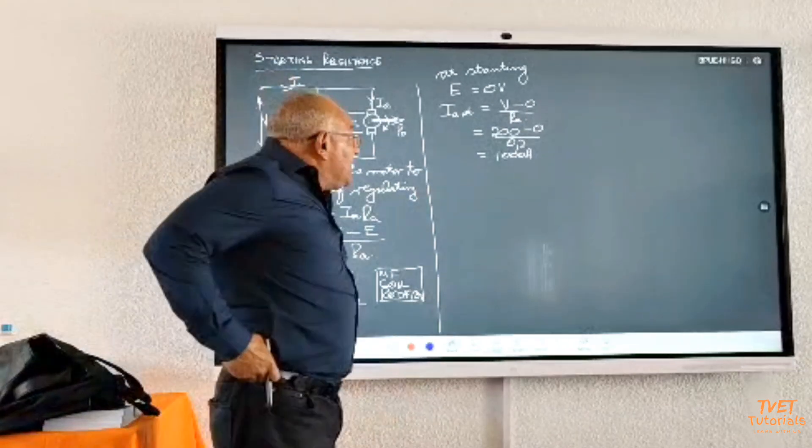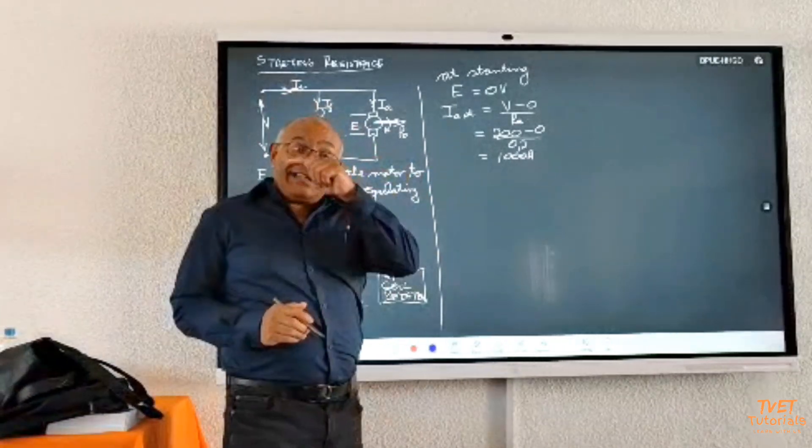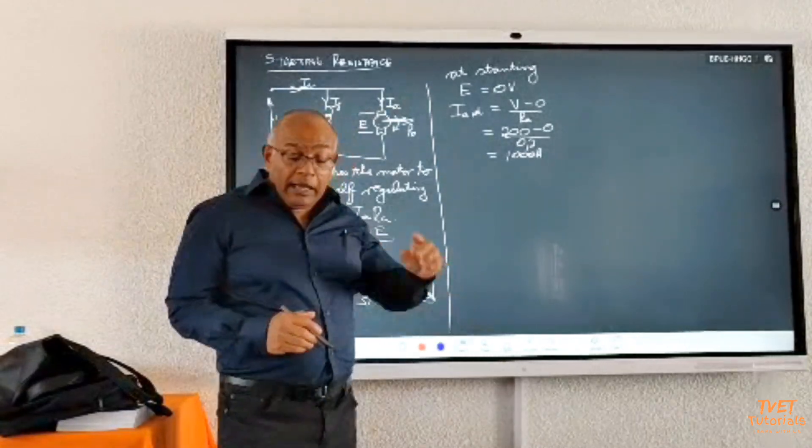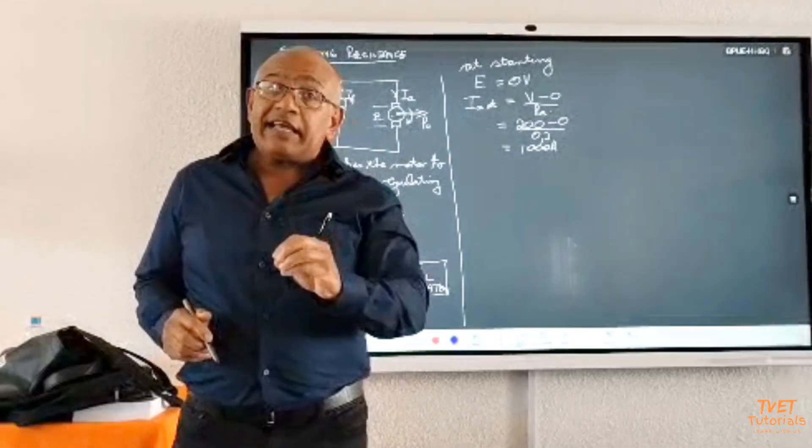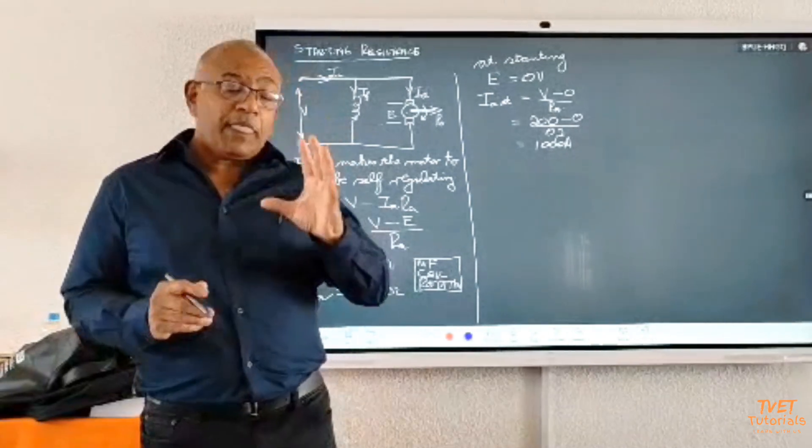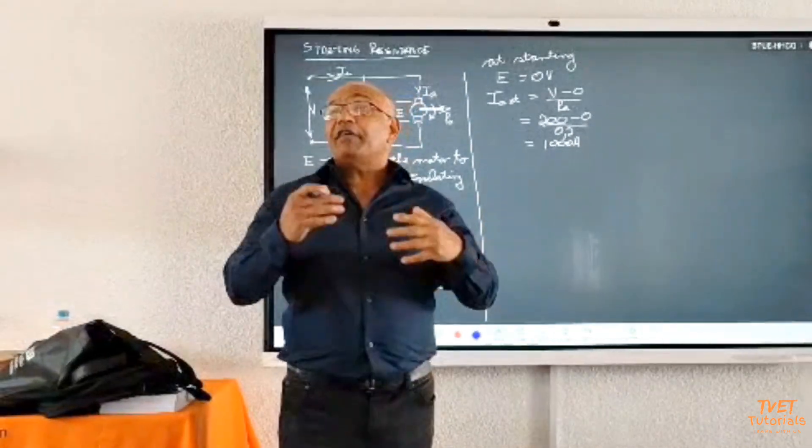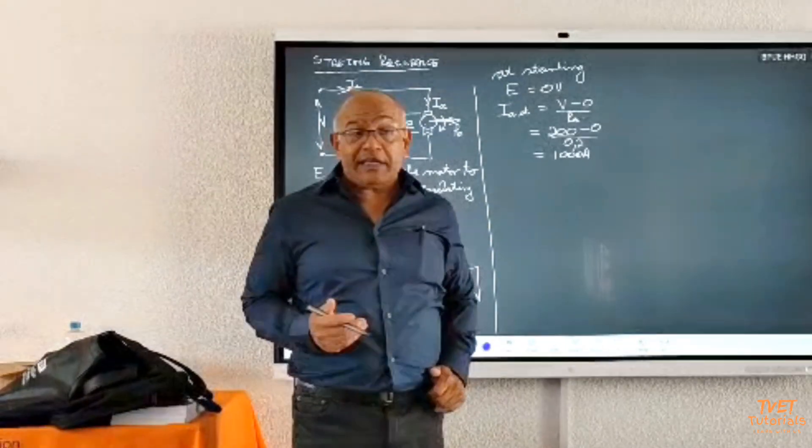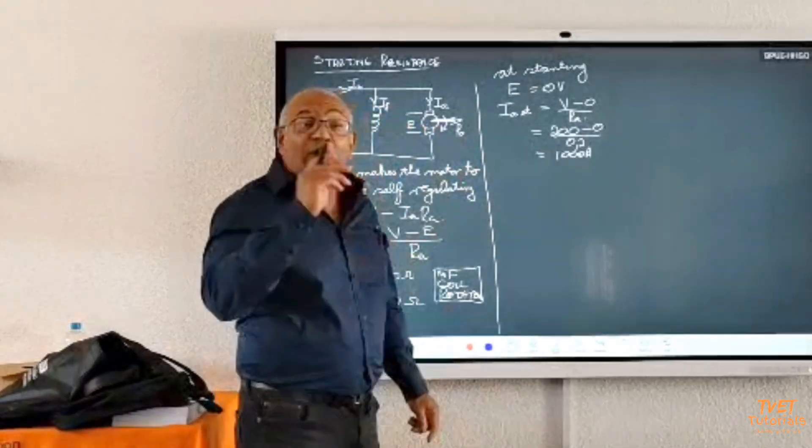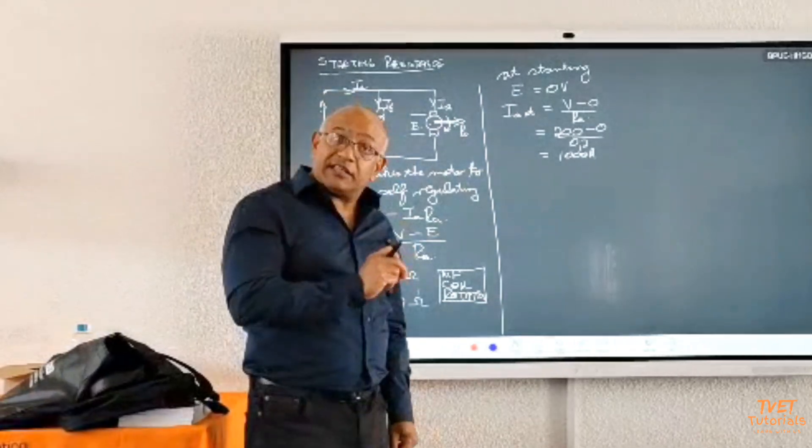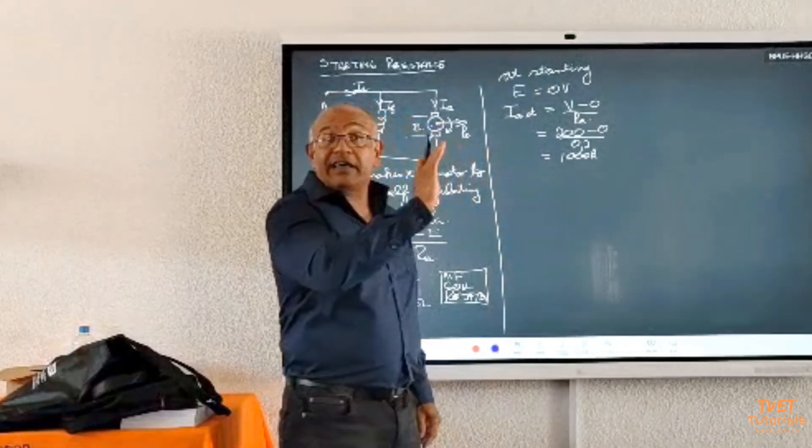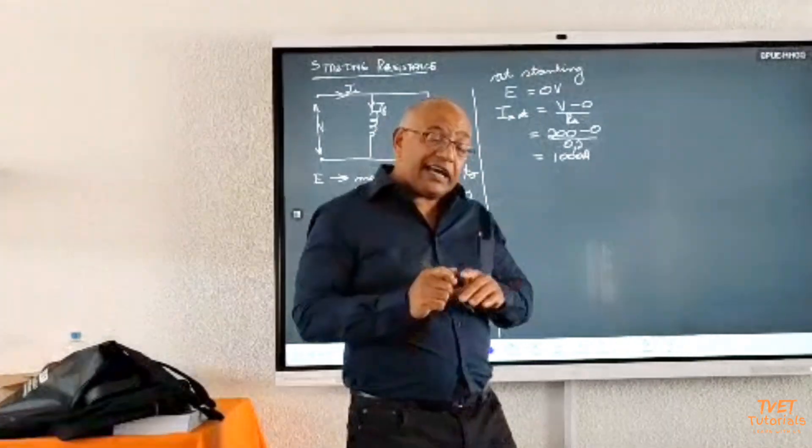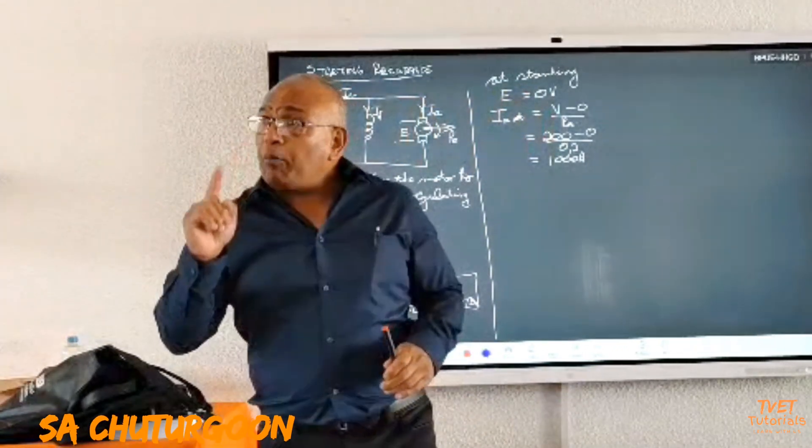That is the reason why we have to bring additional resistance from outside into the armature. But if we make that a permanent connection, the motor will become very sluggish. It will take a long time before it reaches full load speed. That is the reason why we have a resistance starter. The function of the resistance starter is it's a manually operated starter.